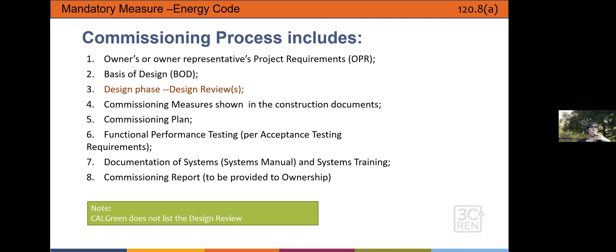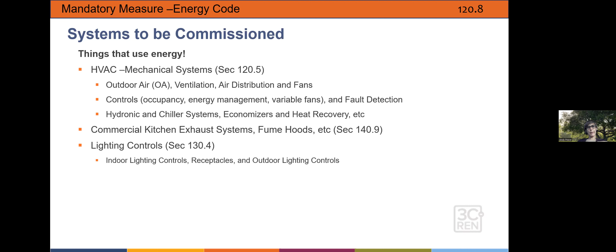So what systems need to be commissioned? The main thing is systems that use energy. Per the energy code, that's all your HVAC, mechanical ventilation, and all the controls that are used need to be checked—hydronic and chiller systems, economizers, heat recovery, etc., domestic hot water, commercial kitchen exhaust, fume hoods, lighting controls, and receptacles.